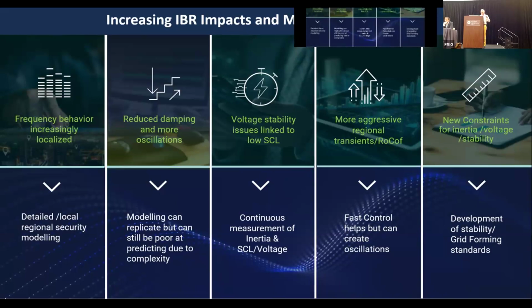You can always tweak the model so that the fault level in the model is the same as the one you're getting on the real system, and you can feed that real-time short circuit level into your online security assessor, so that you know at least the starting point is the real fault level you're seeing on the system.